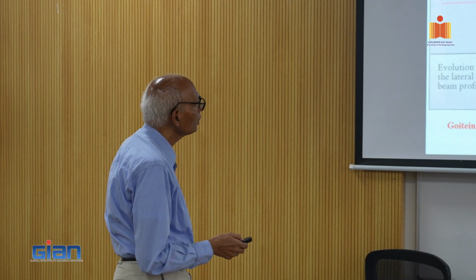So this is what happens. Let's see what your next slide is. So this you will see dynamically what happens. This is the pencil beam here. You have two scanning magnets, and you have a target layer that you want to irradiate. Then you send a spot there, go to a different location, then go to a different location, then you have a different, proximal layer, and in order to bring the energy there, you either choose a different energy from the synchrotron or put an energy shifter or energy degrader there. So if you have energy selection, you select the energy so that the next spot will go to that proximal layer, and you continue, moving from the deepest layer to the proximal layer and put the proton beam wherever it is needed.